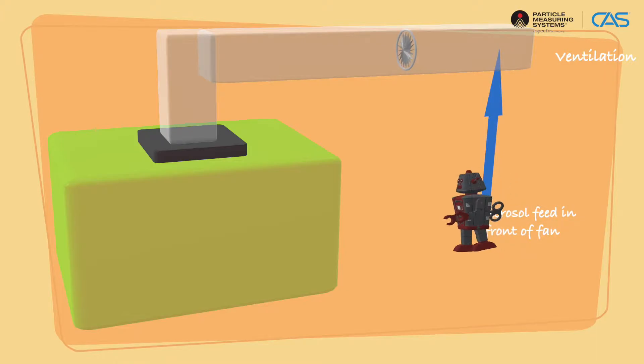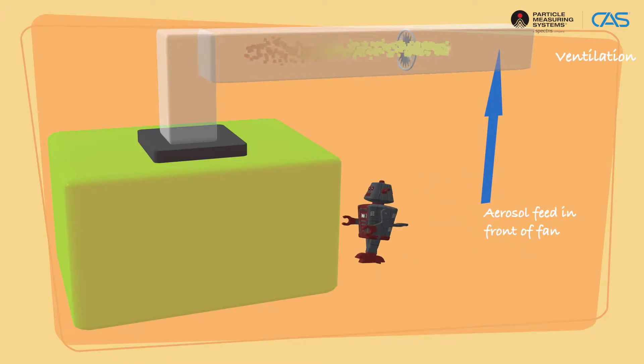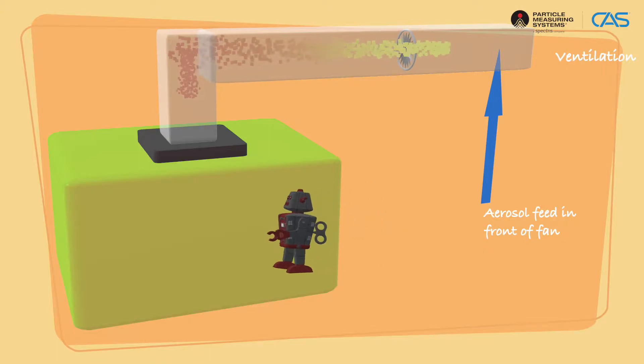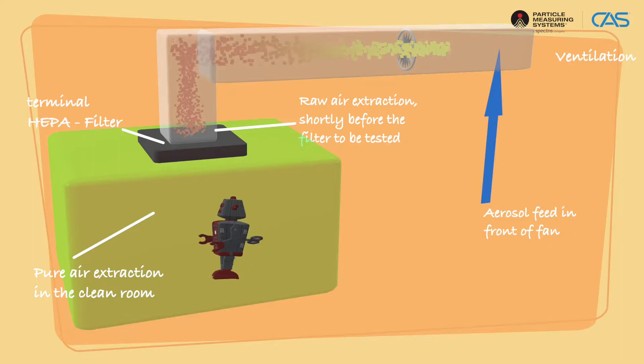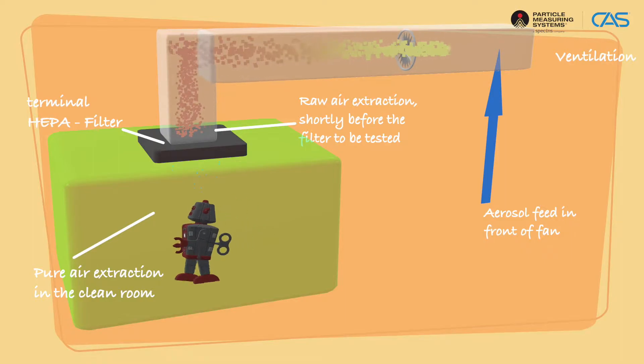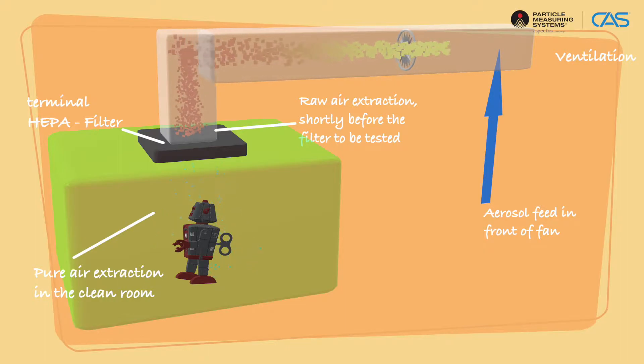At the beginning, the aerosol should, if possible, be applied in front of the fan using the aerosol generator, thus ensuring the ideal mixing of the air with the aerosol. The concentration of the so-called raw air is determined shortly before the HEPA filter is to be tested, with the help of a particle counter and a dilution stage.